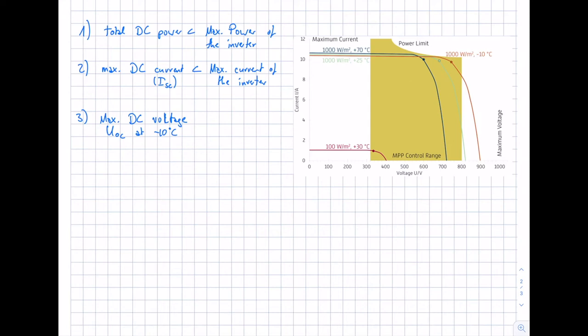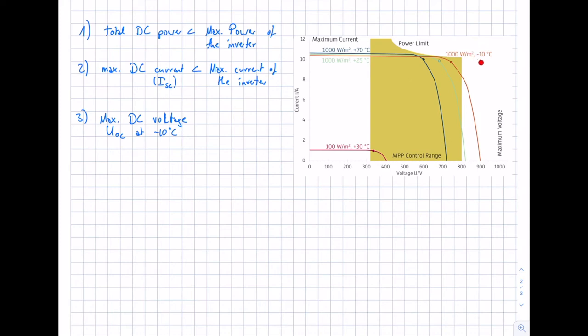The third criterion is the maximum DC voltage that can occur. Keep in mind: if we have a lower module temperature than STC conditions, the voltage will increase. The criterion requires that the open-circuit voltage UOC at minus 10°C must be smaller than the maximum voltage of the inverter. The orange curve in the figure shows the IV curve at 1000 watts per square meter but a cell temperature of minus 10°C, which leads to an increase in voltage.